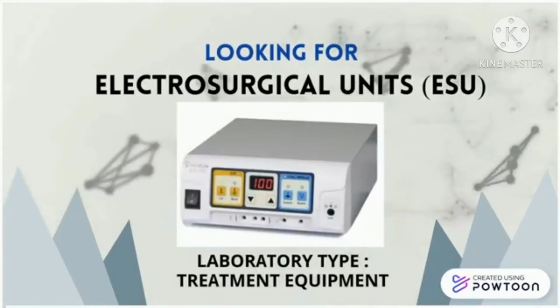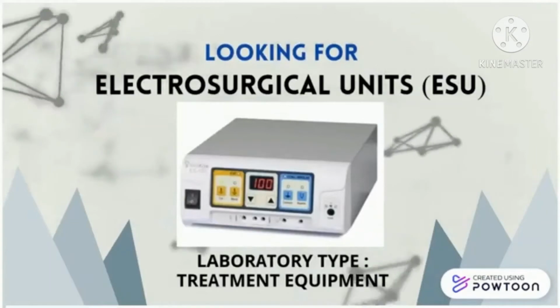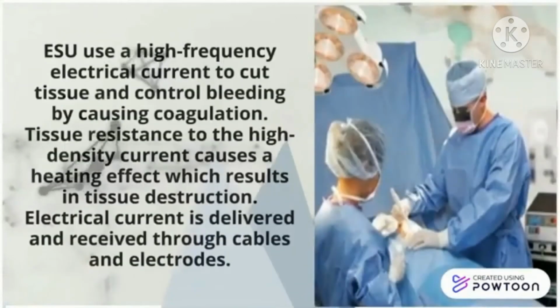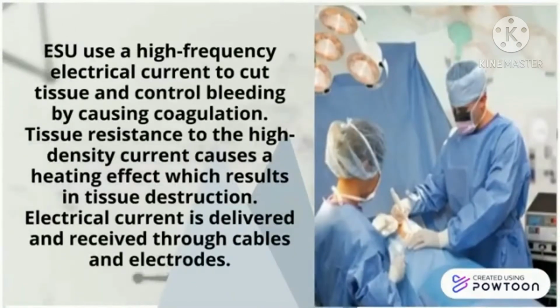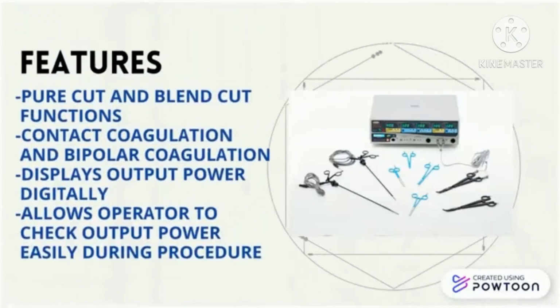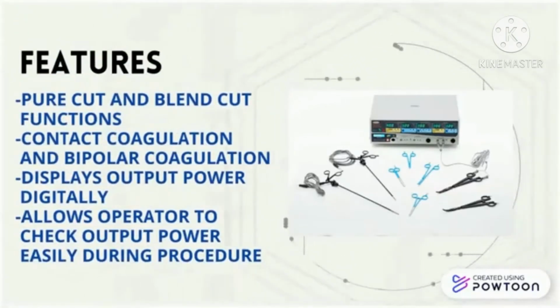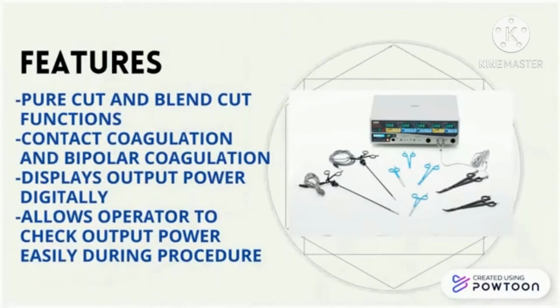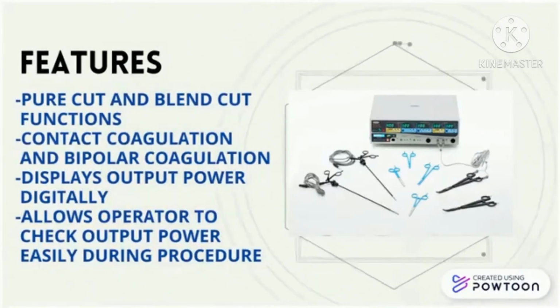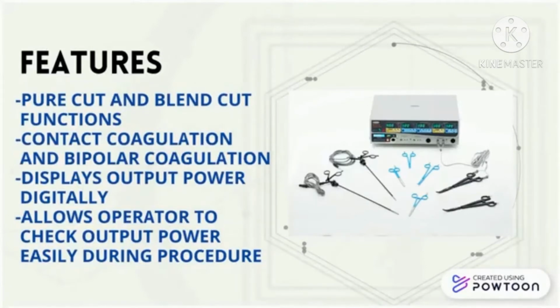Electrosurgical unit, laboratory type in hospital, is treatment equipment. It uses a high-frequency electrical current to cut tissue and control bleeding by causing coagulation. Tissue resistance to the high-density current causes a heating effect which results in tissue degradation. The current is delivered and received through cable and electrode. Features: pure cut and blend cut function, contact coagulation and bipolar coagulation, digital display of output power, allowing the operator to check output power easily during procedure.